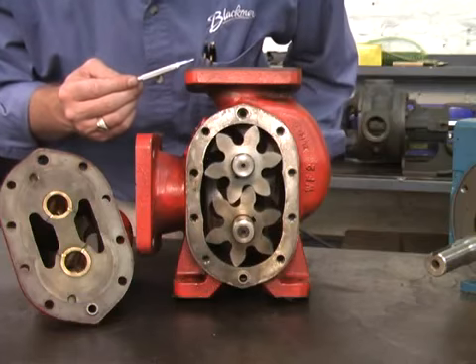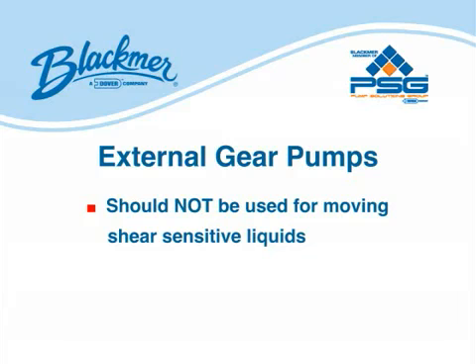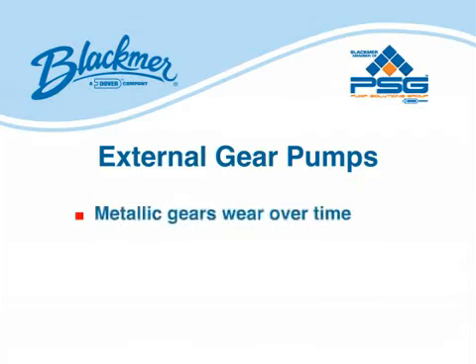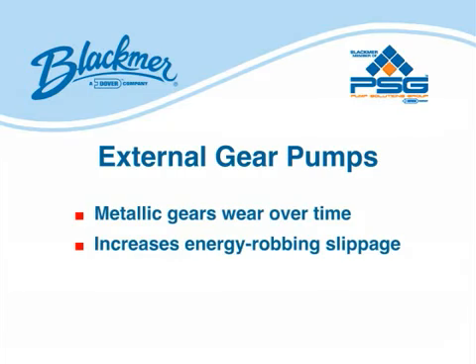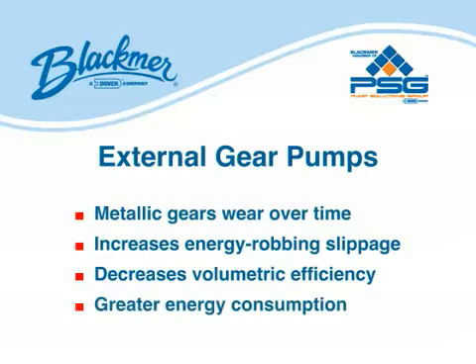However, because the gears actually cut the liquid as it enters the pump chamber, gear pumps should not be considered for moving shear-sensitive liquids. The metallic gears wear over time, resulting in wider clearances. This increases energy-robbing slippage and significantly decreases volumetric efficiency. In order to compensate for the performance degradation, pump speed is increased, which requires greater energy consumption.